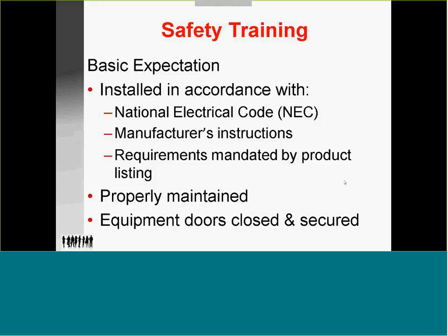the type of equipment. And this is the real catcher: equipment doors closed and secured. Closed door, like on a 480 bucket, latching it, to keep an arc flash explosion from escaping the confines of the enclosure. An arc flash will be hunting for ground, and it can reach out to a person if they're grounded, or to any other grounded equipment. These are done with quarter-turn latches or screws, but they all must be in place once you begin normal operation again.